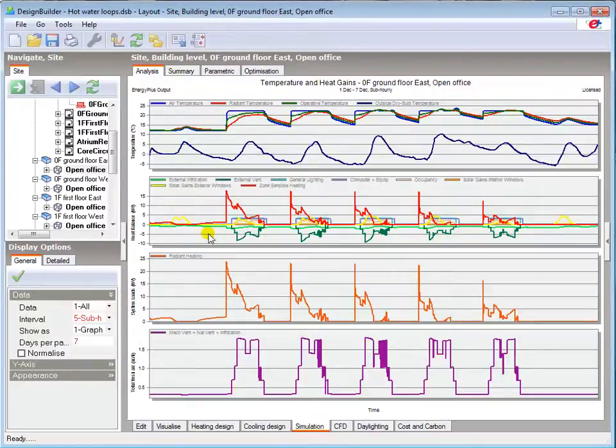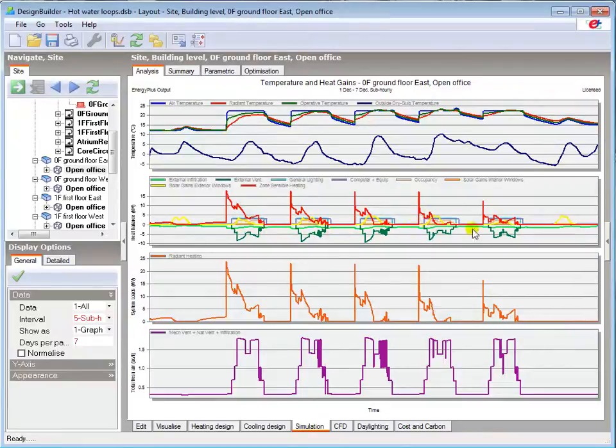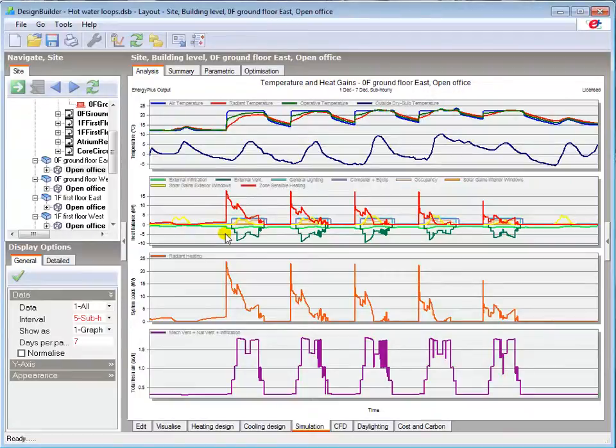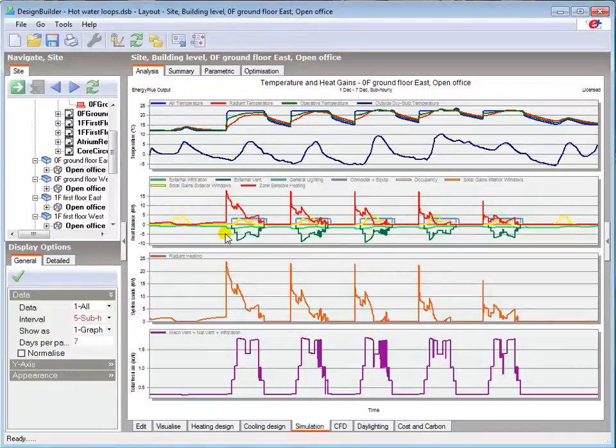The heat balance graph shows the cooling effect due to natural ventilation, which has to be offset by the heating system to maintain the heating setpoint during occupancy. Note how the cooling profile is similar to the fresh air profile below.